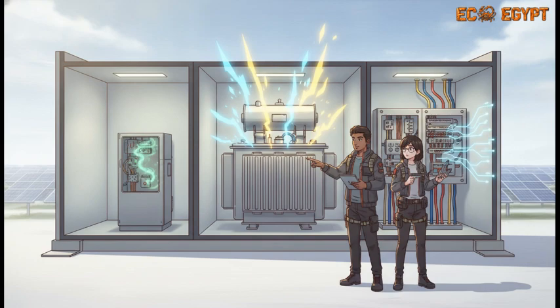Then you have the actual power transformer. This is the heavy lifter. It takes the 0.8 kilovolt output from the inverters and steps it all the way up to 33 kilovolts. And finally, room number 3 is the MDB, the main distribution board, which basically manages the local low-voltage distribution back out to the inverters and those auxiliary services we just talked about.